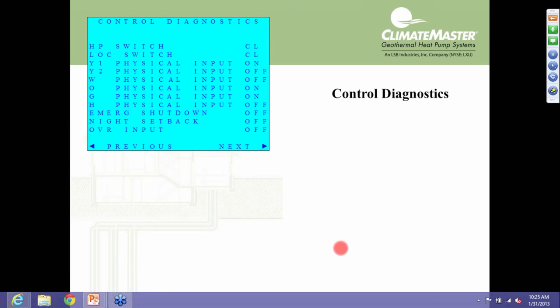Now, once we get it running, so we can actually see what our temperatures are, and if we've got a variable speed pump, if the pump is running between 50 and 90%, we can actually see GPM. We can read our feedback signal from the pump and display gallons per minute on the screen. So now we'll have gallons per minute, our entering water and leaving water temperature on the screen. We've got almost everything we need in order to do our heat of extraction, heat of rejection calculation that we're going to do here shortly.